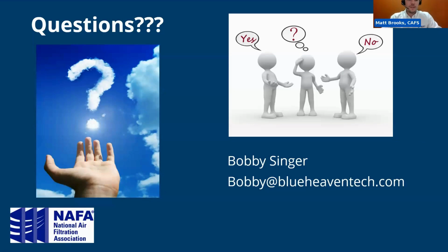Awesome. Okay. And in regards to pressure drop, there are a couple people asking about pressure drop in your system compared to a real world system. The test duct you have has a designated, or at least a controlled volume and velocity of air, and that's adjustable. Or in that testing, is there always a standard amount of air at a standard speed that you're using for the 52.2? No, it's adjustable.